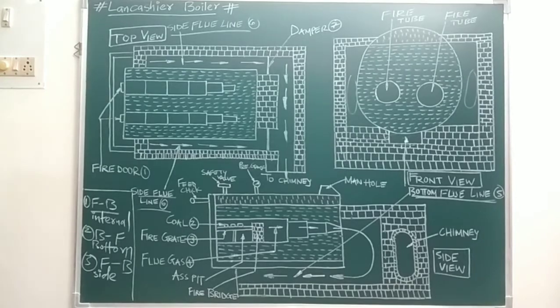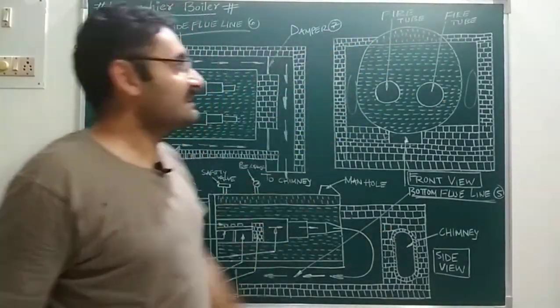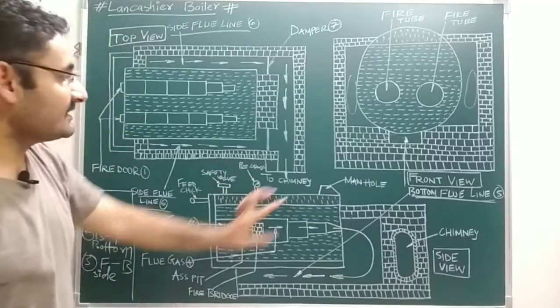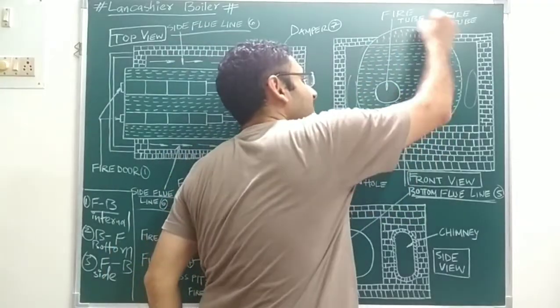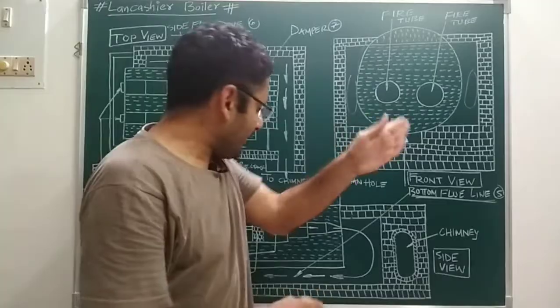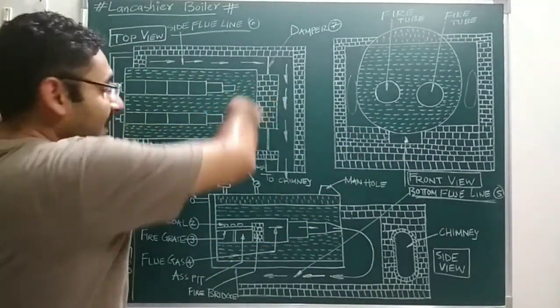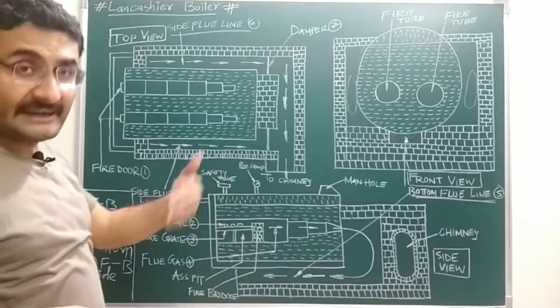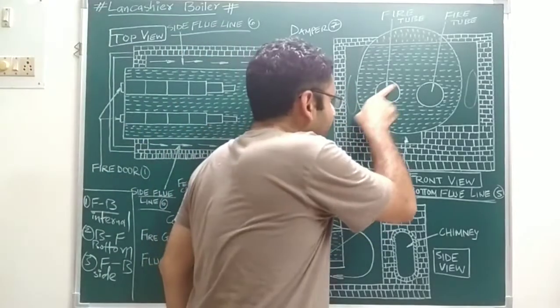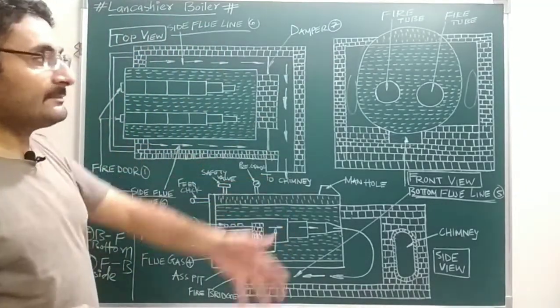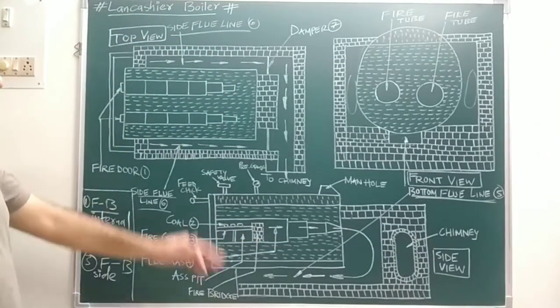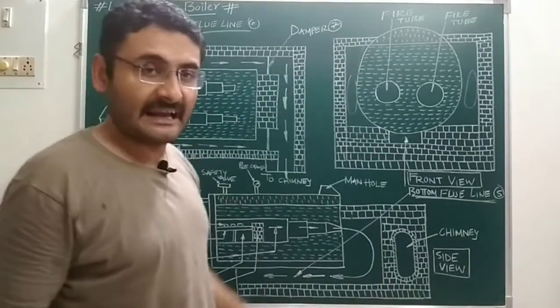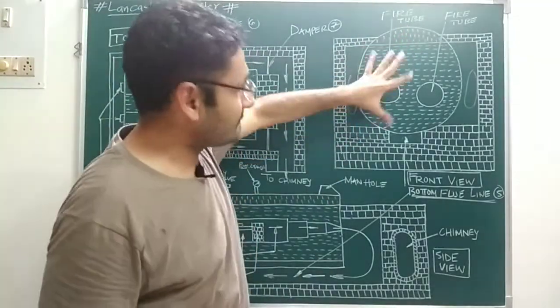With the help of these three stages, heating of water takes place and steam is generated at the top of the shell. The diameter of the shell is around 2 meters and the length is around 8 to 10 meters. The diameter of the fire tubes is around 80 to 100 centimeters, and the length of the fire tubes is also around 10 meters, matching the shell length.